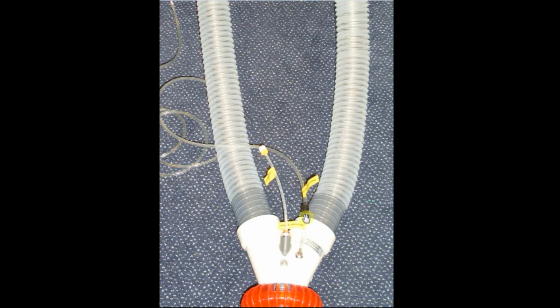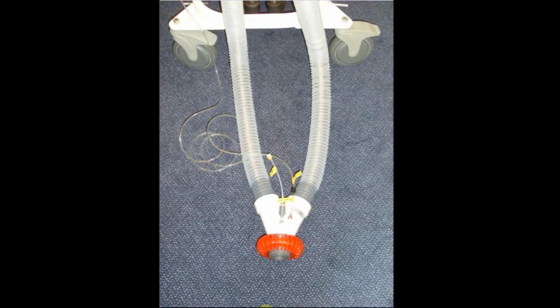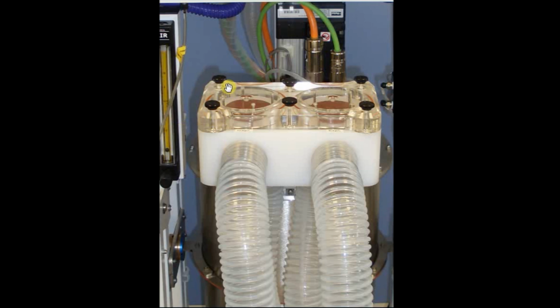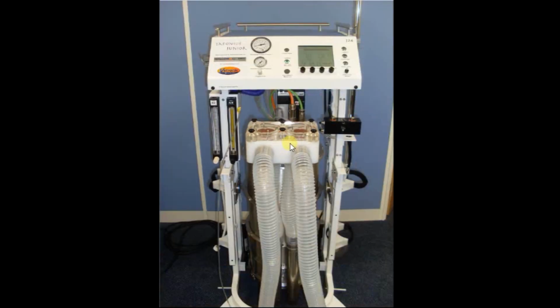If this sensor isn't connected, then the machine will still function, as we have an auxiliary sensor which is actually coming in at the back of this valve block and will measure the pressure. But as you can probably appreciate, the pressure measured at this point isn't so good at controlling the airway pressure at the Y piece as it is directly at the Y piece. And so the machine, although it will function, will behave not as well as normal, and the pressure variations will be much greater in the patient's circuit than you would expect.